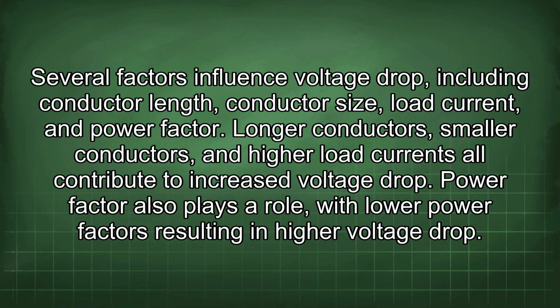Several factors influence voltage drop, including conductor length, conductor size, load current, and power factor. Longer conductors, smaller conductors, and higher load currents all contribute to increased voltage drop. Power factor also plays a role, with lower power factors resulting in higher voltage drop.